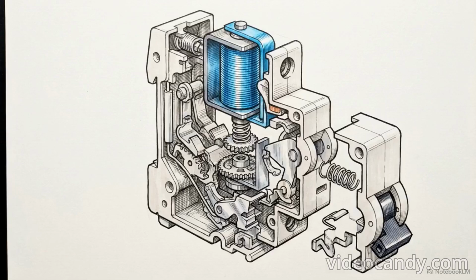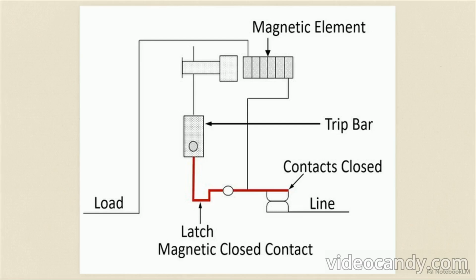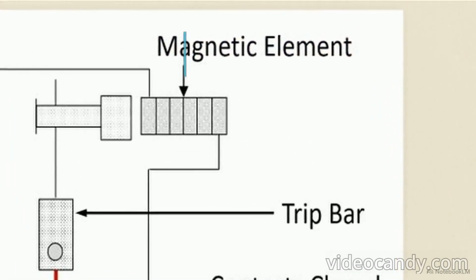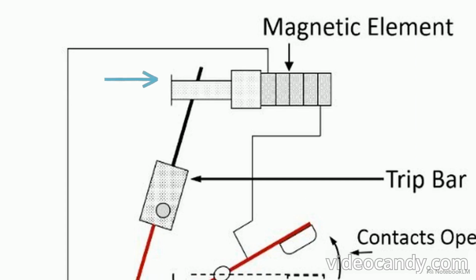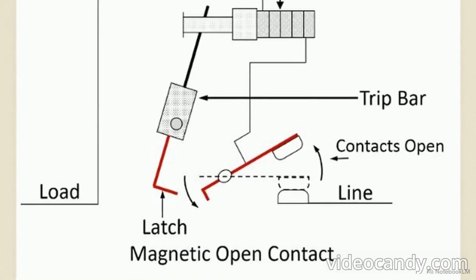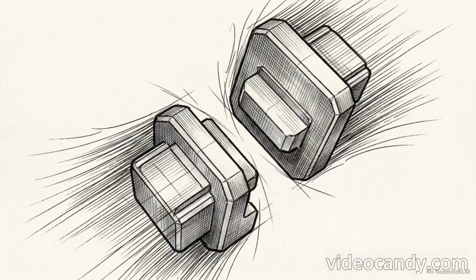That thermal bend is perfect for slow overloads, but a dead short circuit requires immediate interception. That introduces stage 2, magnetic operation. Looking at the internal schematic in the closed position, you can trace the load path directly through the second sensing component, the magnetic element, or solenoid. When a short circuit hits, the massive instantaneous spike in current rushes through the wire coil of that solenoid. Because magnetic field strength is directly proportional to current, this creates a powerful magnetic field instantly. The field generates immense physical force, driving an iron plunger forward like a piston. It strikes the trip lever directly, releasing the latch mechanism and violently separating the contacts. This mechanical sequence occurs in less than 10 milliseconds.